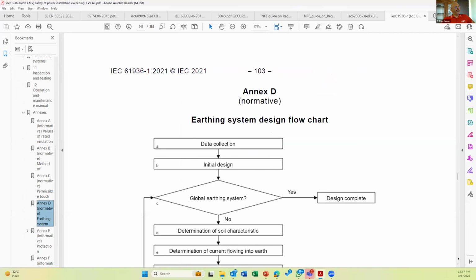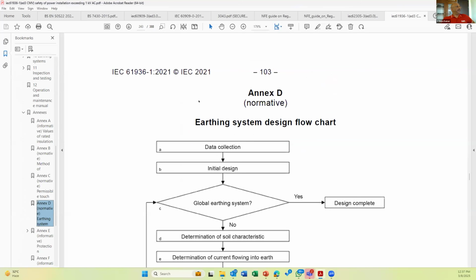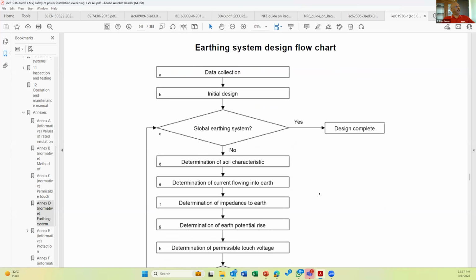This is how we are supposed to make earthing. What are the steps to be followed while making an earthing system for more than 1 kV AC? Earthing system design flowchart: data collection, initial design, global earthing system, yes, design complete. It means if you are in an industry or a part of a large building, then the recommended measure is to go for a global earthing system where LV, HV, ELV, lightning protection, everything is interconnected together. Global earthing can be achieved where the touch and step voltages are within the limit. Yes, design complete, very easy.